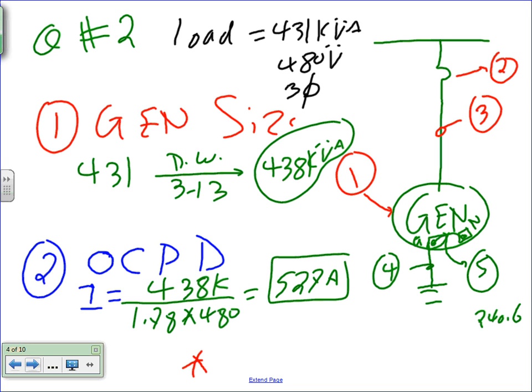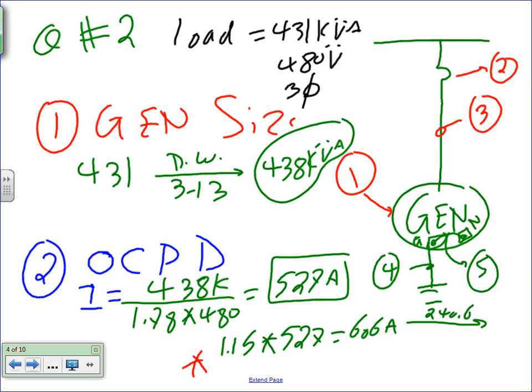Then you're going to take 1.15 from the generator code, multiplied by 527. That will get you 606 amps. And I know for 6 amps, some of you might say, Chad, I'm going to go to 600 amps. Yeah, 6 amps. What's your next standard? If you take it to the next standard, which is 240.6, the next standard will be 700. Now, some of you said, Chad, I'm going to put 600 because 6 amps I can digest, right? So that's okay. Write it down and it's okay for me. 700 amps. But I'm just going to go strictly by going to the next standard.